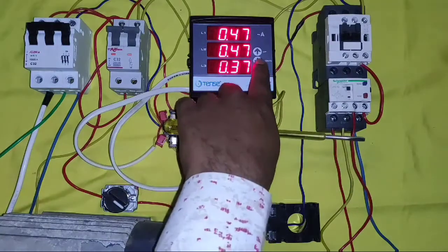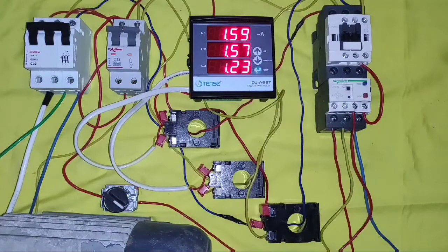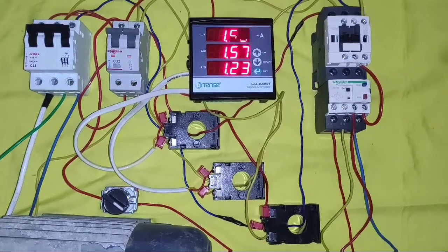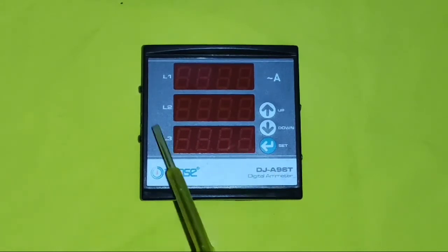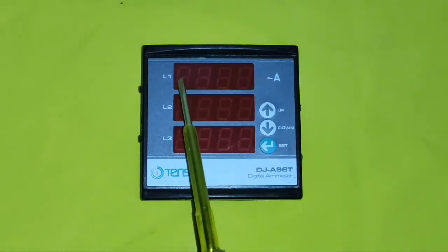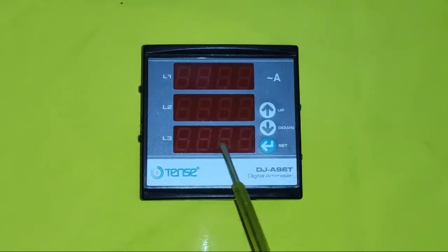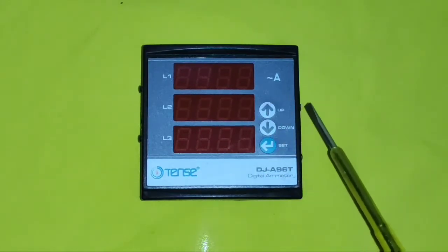In this video, we use a 50 by 5 ratio CT, so we need to set the upper ratio of the current transformer, which means we set 50. Your current transformer ratio should be correct; otherwise your current measurement will not be accurate. We use the Tense Electronics DJA 96T model digital ampere meter. Tense Electronics is a Turkish electronics company that makes good quality electrical and electronic products. You can watch all 3-phase ampere readings here in L1, L2, L3.